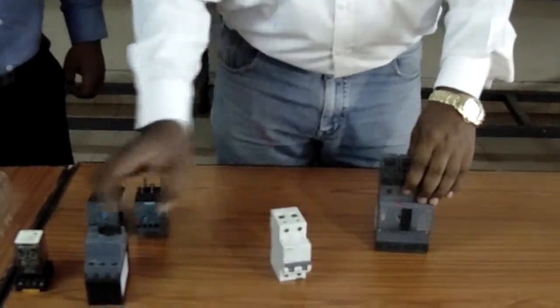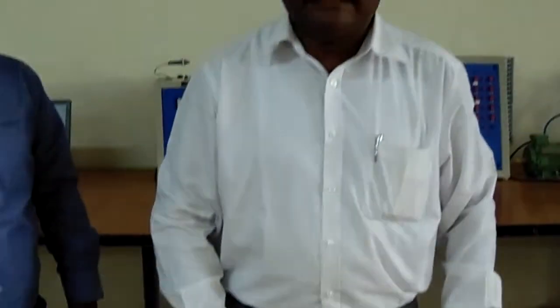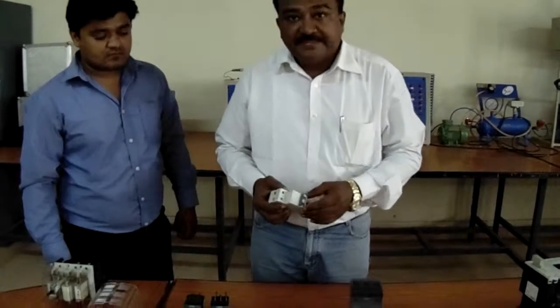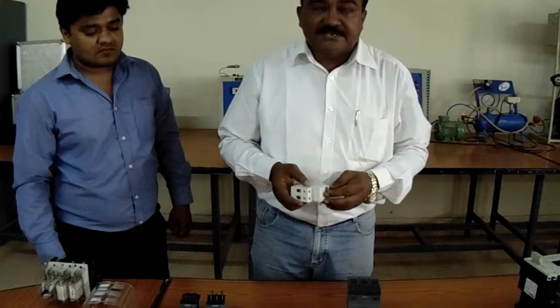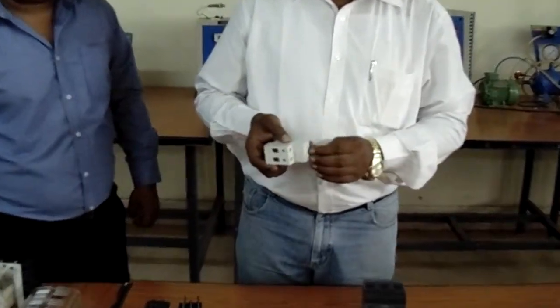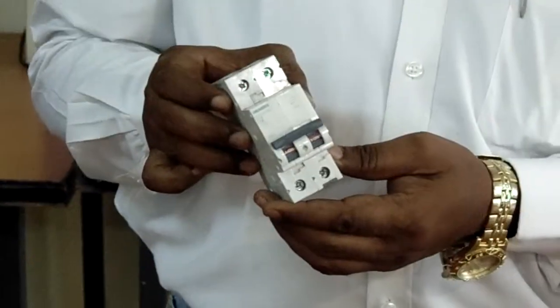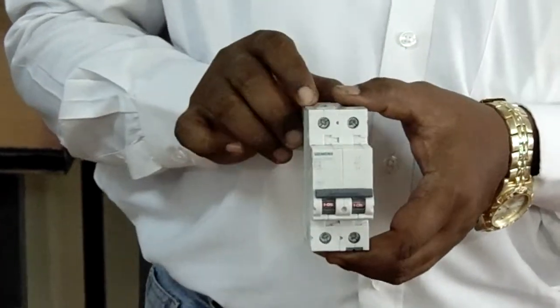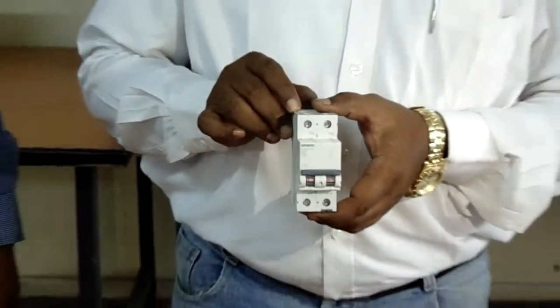Now, coming to fuseless isolators, the difference between fused isolators and fuseless isolators is that, in the event of any problem, you do not have to replace the faulty components, you just have to reset it. In the fuseless section, the isolators start from miniature circuit breakers, MCBs. MCBs are very commonly used in domestic applications and for current ratings up to 32 amperes. These miniature circuit breakers are available up to 63 amperes.